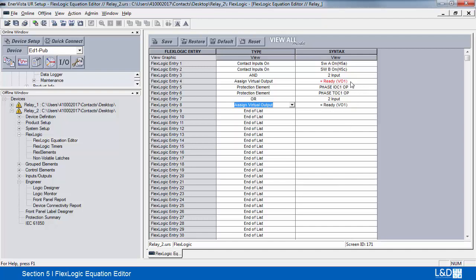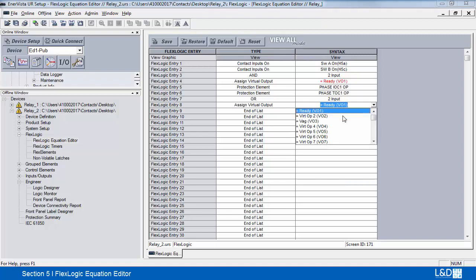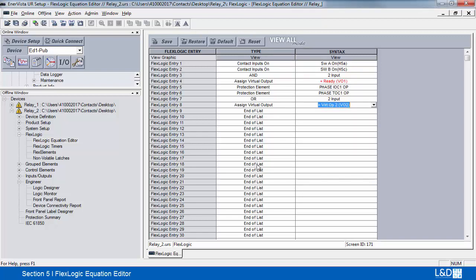You can see this virtual output has become red, because the guidelines in FlexLogic are that we cannot duplicate. We cannot assign the same virtual output to two different equations. So we'll assign this to the second one, and this one clears.